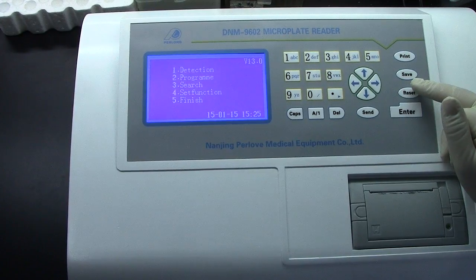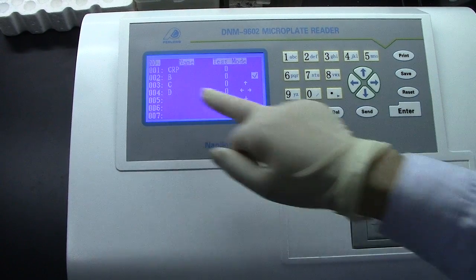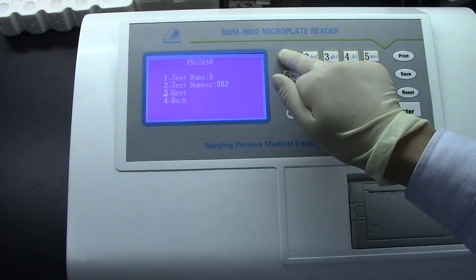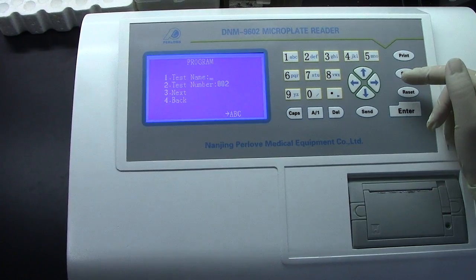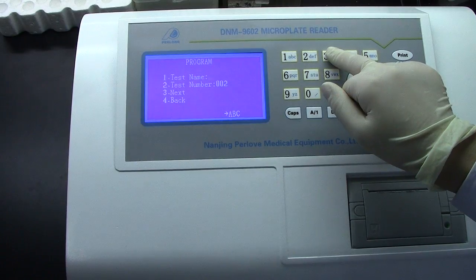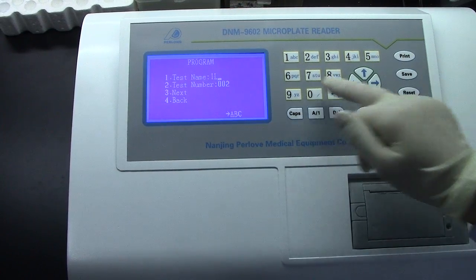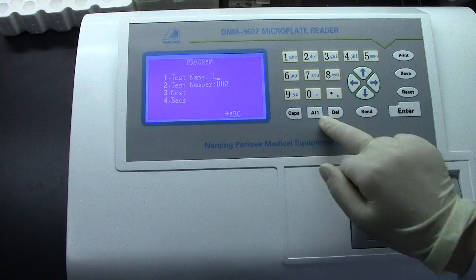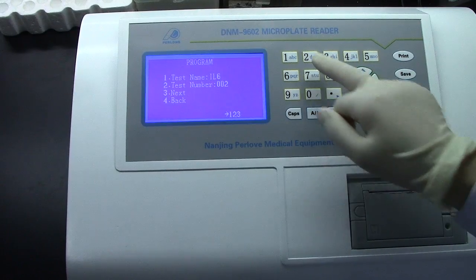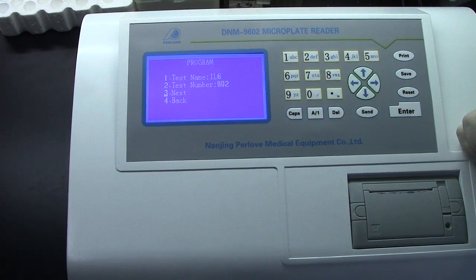Let's do program 2 — a new one. Press this. Here, 002. Press Enter to change the name. We want to input IL6. Press Enter to confirm. The test number 002 is OK.